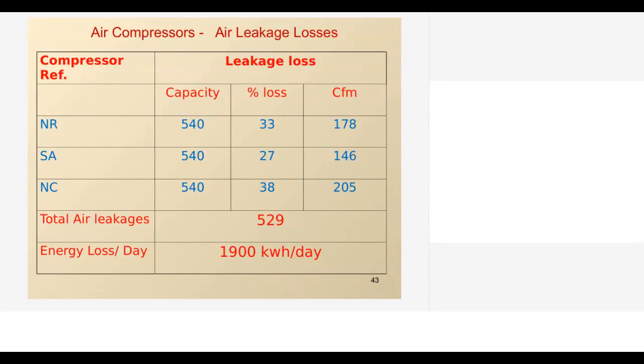Second thing, for good compressed air management, you should always have monitoring of all the compressed air usage points. Because what we have found, in any industry, if we ask where you are using compressed air, they will say it starts from vehicle parking up to effluent treatment, we have air connections. That is all fine. But if you want good compressed air management, you first start numbering all the user points. Once you have numbered all the user points, when any leakage is there, you can attempt to fix it.